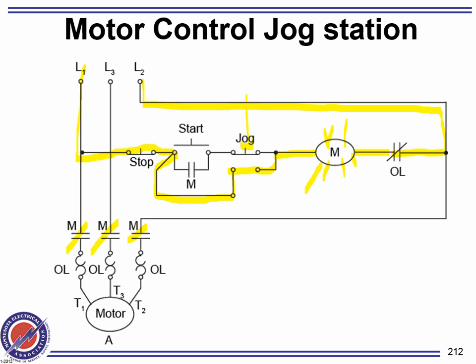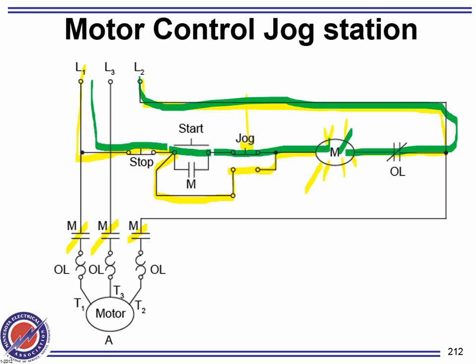Now the starting mechanism is slightly different, of course. For the starting, you push the button here. Now the current is coming from the same direction in here, all the way through the coil. It goes all the way back. And now to continue energizing it, this will close and bypass the momentary start station button.